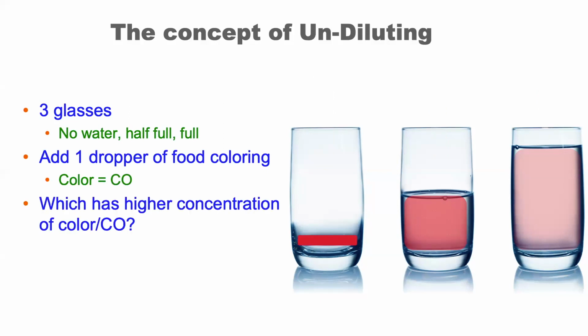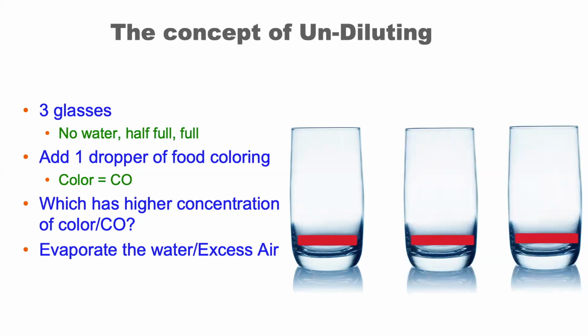So which one has the higher concentration? Of course, it'd be the one that's the darkest color. It has the highest concentration of CO. It's got nothing diluting it. If we could evaporate the water, which means removing the excess air, we'd have the same amount in each. So the process of undiluting or providing an undiluted sample allows you to get a consistent level of the actual CO being produced in the system before it's being diluted. That's the purpose of doing this, so that measurement to measurement can be done consistently.